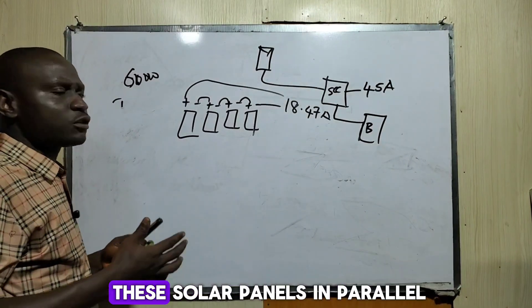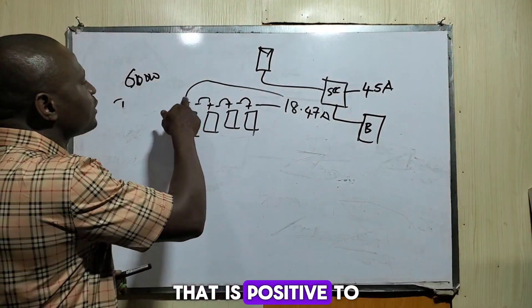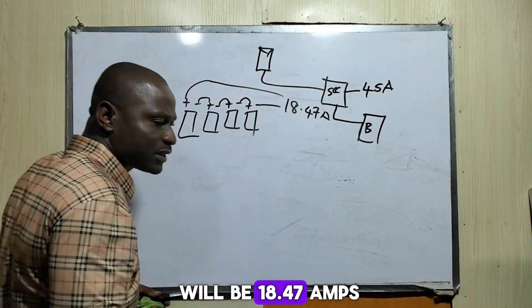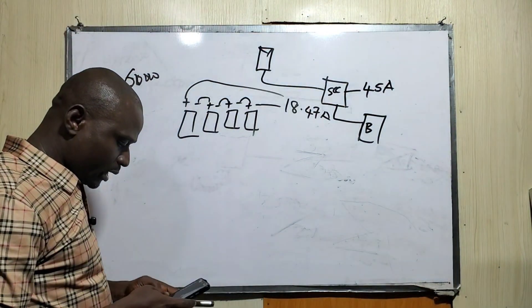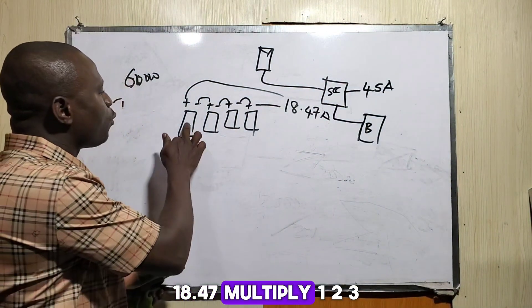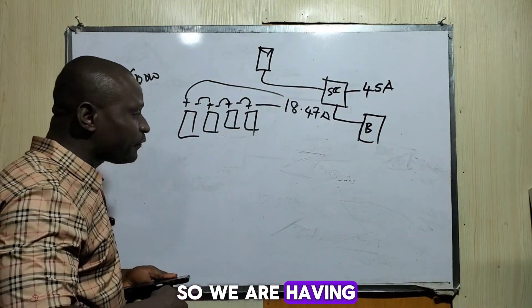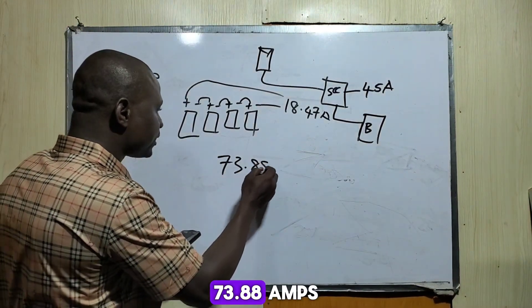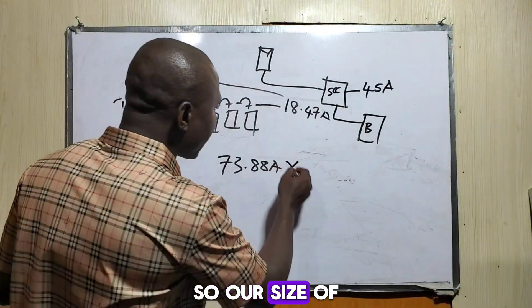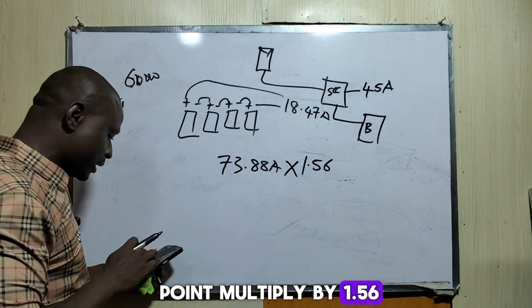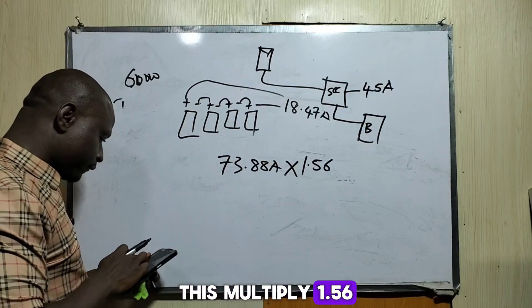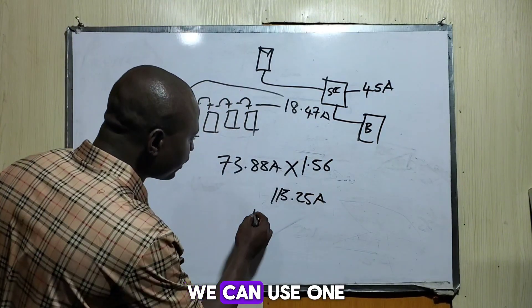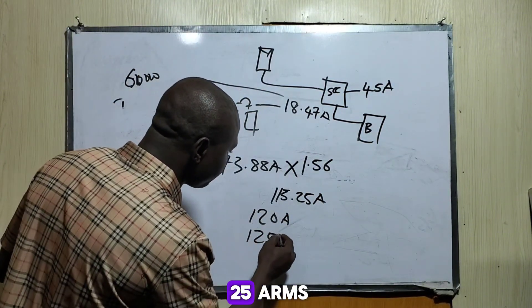But if we connect those four solar panels in parallel — positive to positive, negative to negative — the total short-circuit current becomes 18.47 × 4 = 73.88 amps. Multiplied by the safety factor of 1.56, this gives 115.25 amps. So we can use a 120-amp or 125-amp breaker.